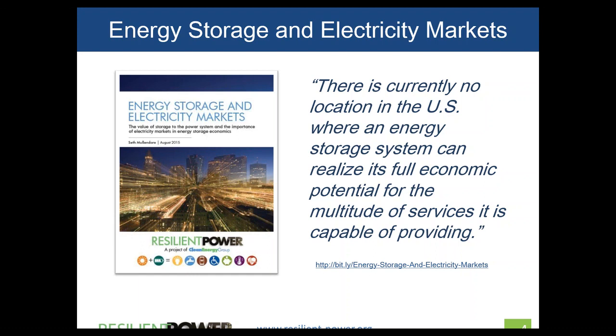What we do on top of that is: if you have a network of megawatts of batteries ranging from commercial truck batteries and 100-kilowatt C&I batteries to five-megawatt municipality systems, our balancing algorithms maximize efficiency and battery use. For example, with 10 megawatts playing in regulation, we're not using one 10-megawatt battery — we've got building blocks. When the reg signal is 4 megawatts, we're using a subset at 100% efficiency rather than everything at 40% efficiency. Doing this for regulation, reserve, and wholesale capacity prolongs battery life, improves efficiency, and exemplifies the value of a network.